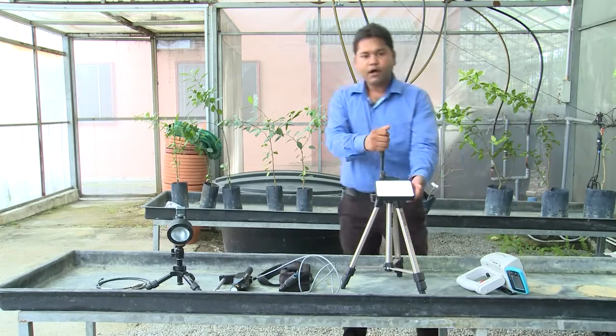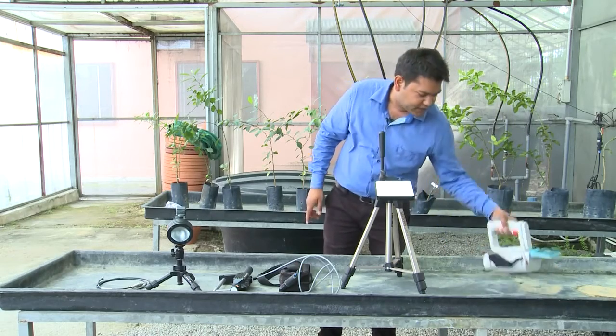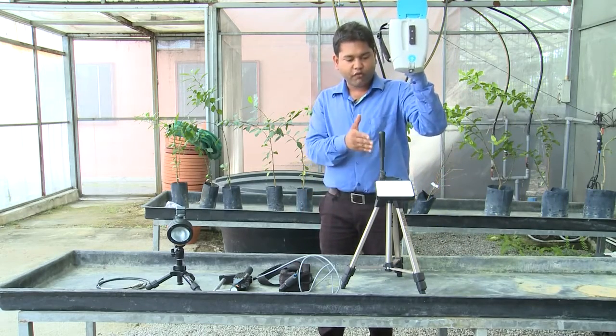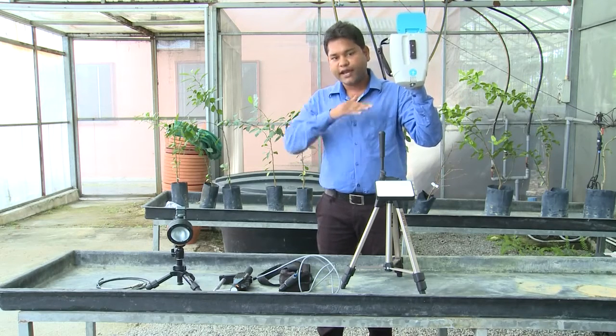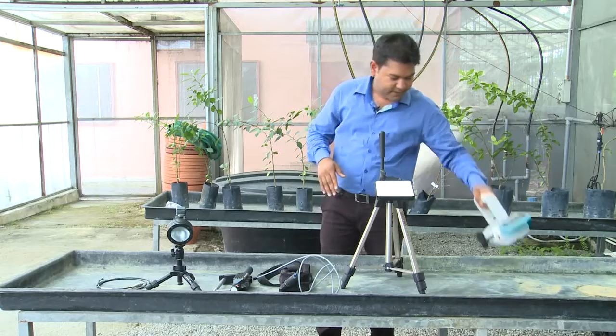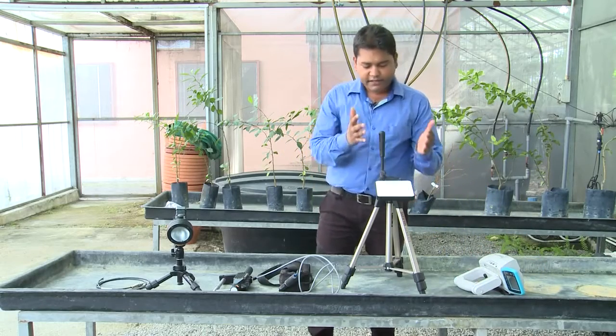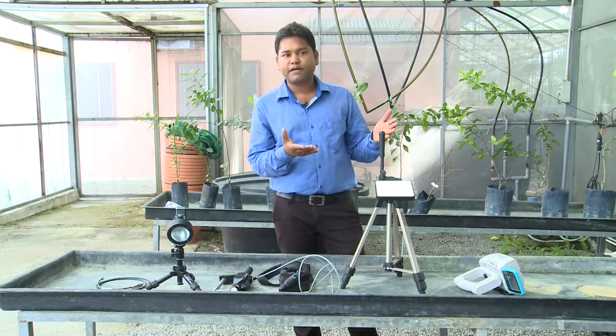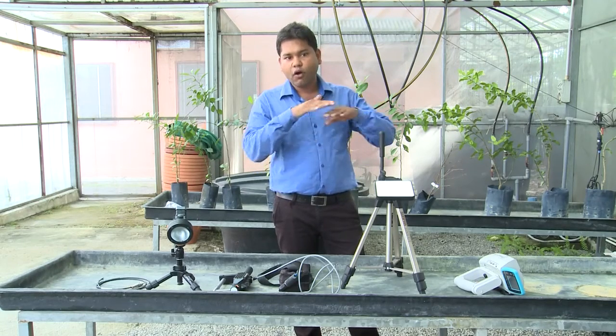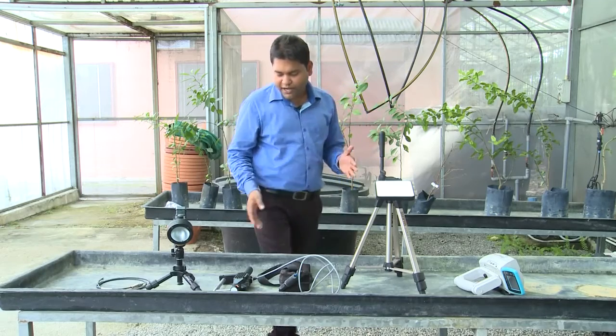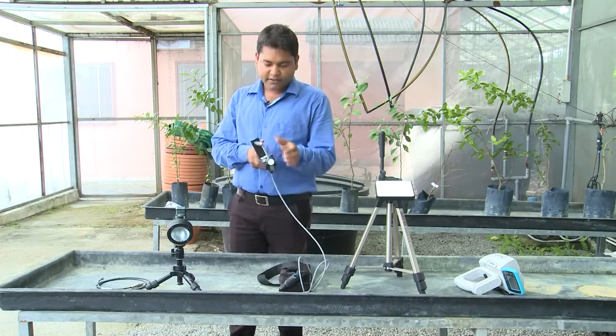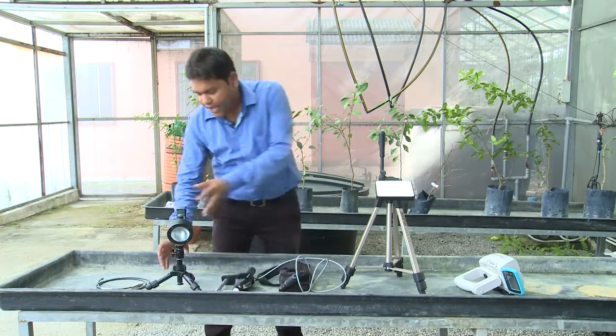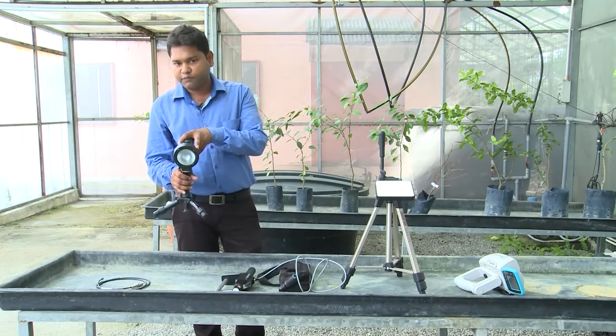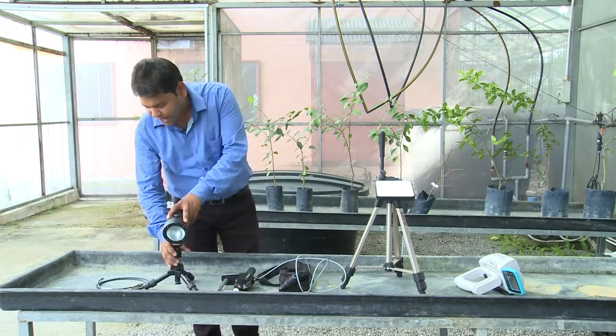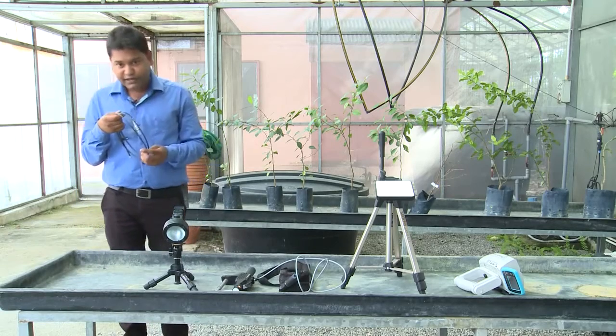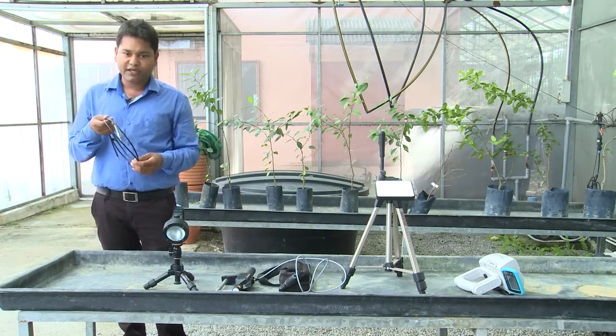It's called the white reference. Generally we target the FieldSpec 2 toward the white reference for optimization and to collect the white reference. The white reference is made with a material that gives 99% reflectance over the spectrum range. Another component is the plant probe with leaf clip, and there is a halogen light for diffuse reflectance measurement in the lab. And a very basic, important component is the fiber optic cable.